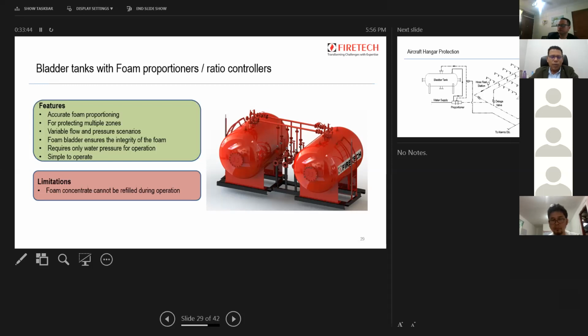It requires only water pressure for operation, so you don't require an electric motor or a diesel engine. And it's very simple to operate. Just open the valves and the foam mixing will happen on its own. It has only one limitation, that is the foam concentrate cannot be refilled during operation. So such systems are generally designed for the complete duration of operation.